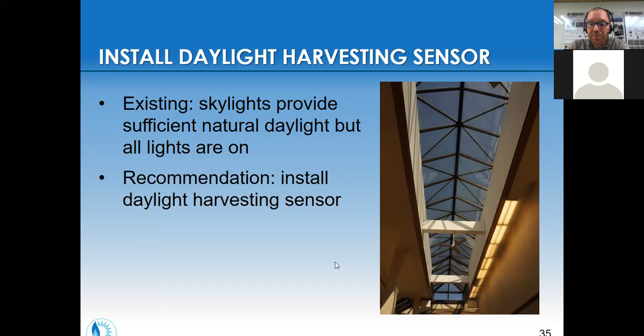In this example, we have a beautiful library space with 32-watt T8s, and they felt they had too much light. They'd done analysis with a light meter and found their light levels were higher than needed—closer to 100 foot-candles when they could be in the range of 20 to 50 foot-candles. The ballasts they already have are capable of driving a 25-watt T8, so going from 32 to 25-watt lamps—slightly more expensive per lamp—will save energy and provide a nicer light level.